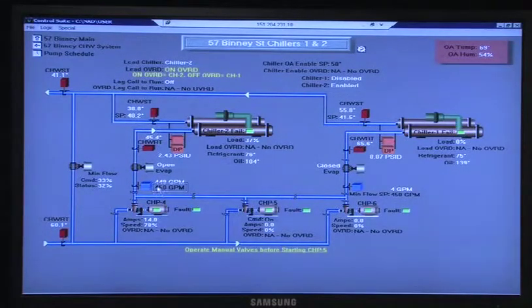That's why we had to maintain that. They used to have paddles in there, and the paddle failed. There is a DP, but it's part of the Trane package. Yeah, it's all run by Trane. This is important because across the chiller bundle, to get the right DPs and all that, they want to maintain 450 GPM. So where's the bypass valve?